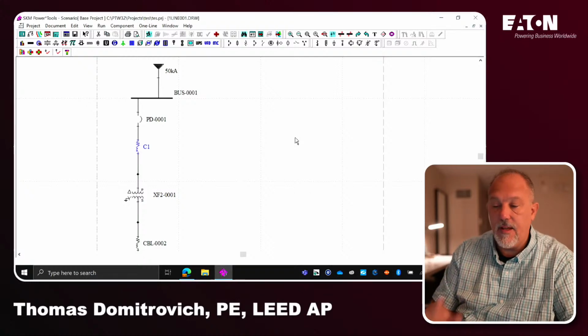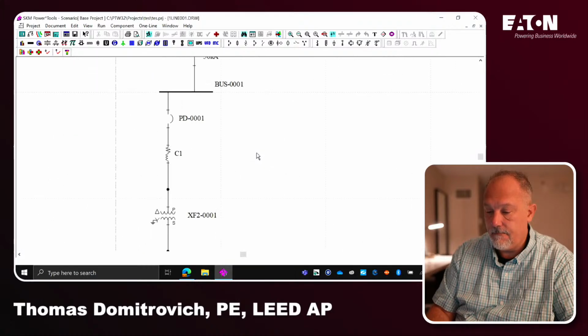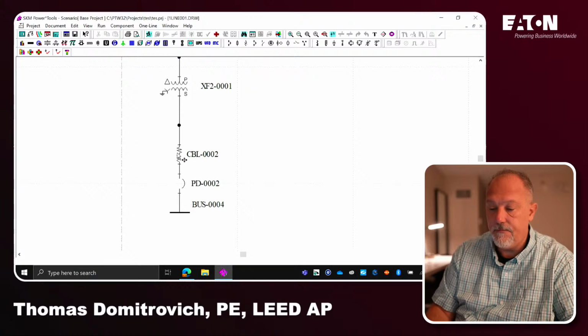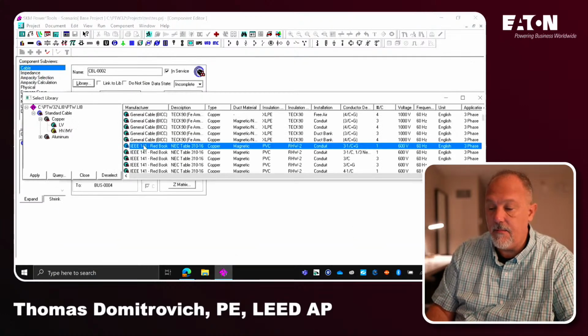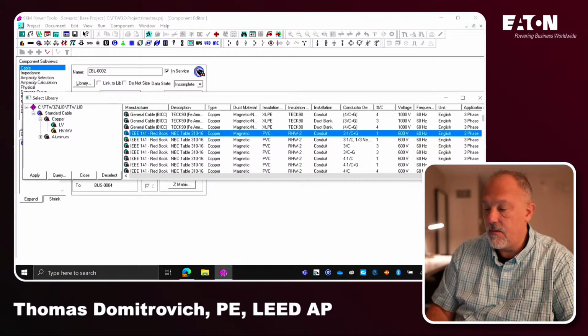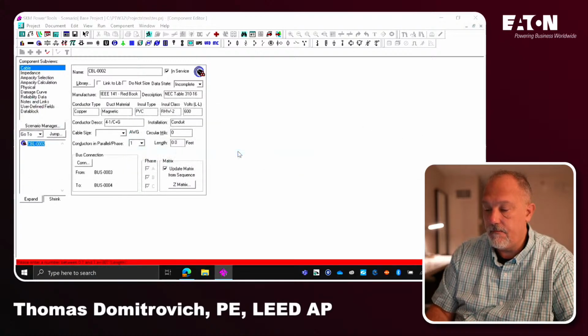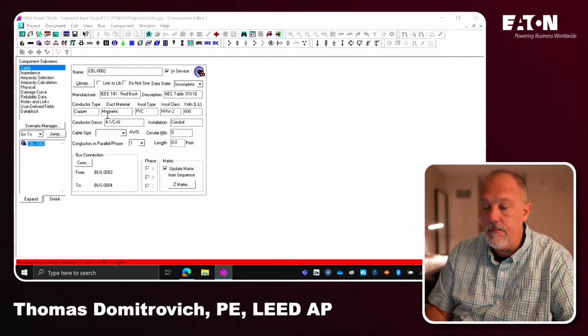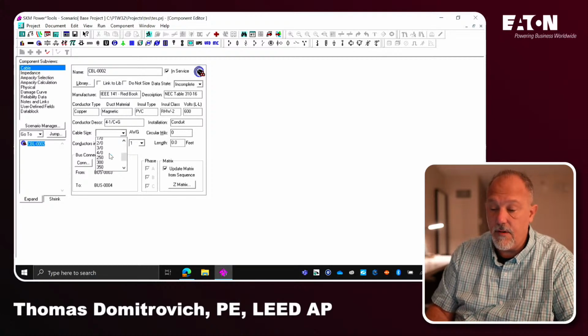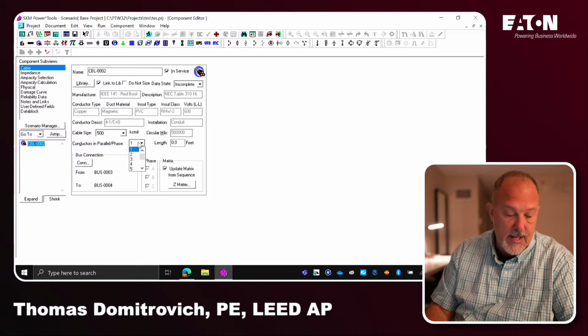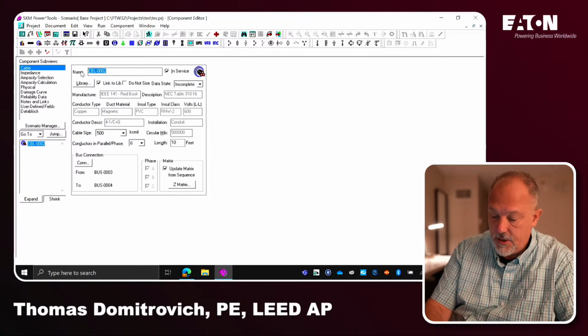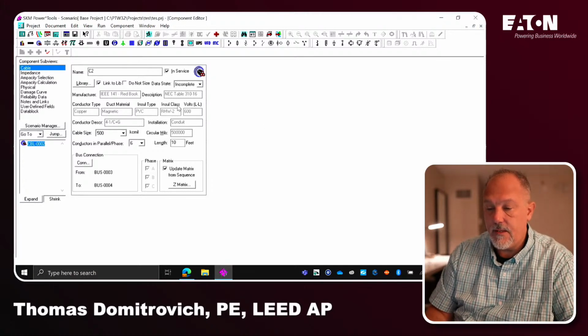So we have our conductor 1 defined, we have our source impedance defined, and now the secondary conductor. If you recall, for the secondary conductor, I'm going to pick the same. Whoops, no, I can't pick that one. I have to pick 4 because it's a delta-Y ground. 4 single conductors plus ground. Now cable size, we said was also 500 MCM. We said that we had 6 in parallel. And we said the length was 10 feet. All right, and we will call this shift C and the number 2. All right, we are golden.